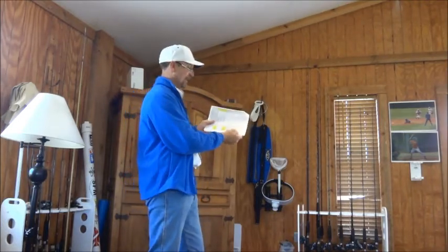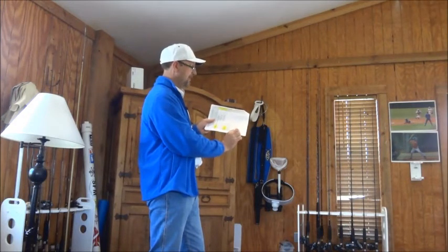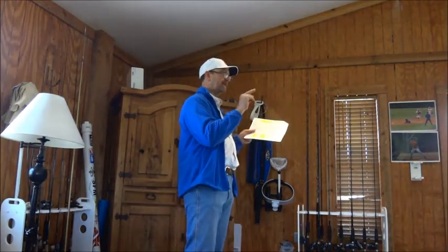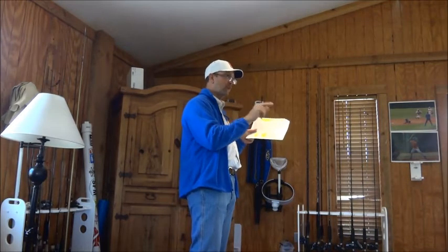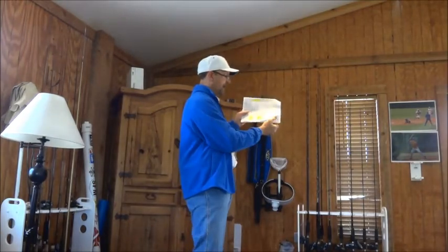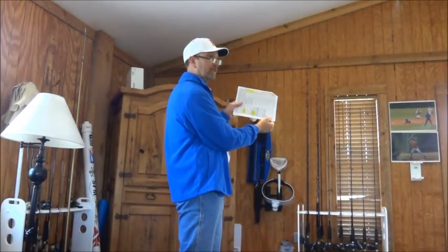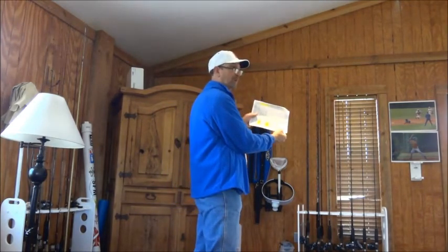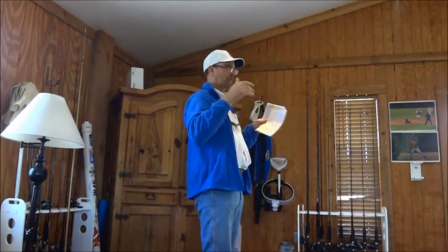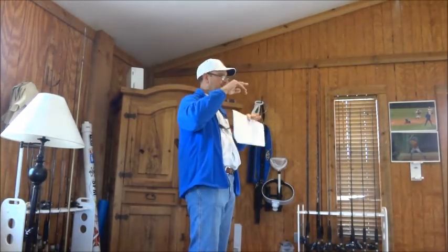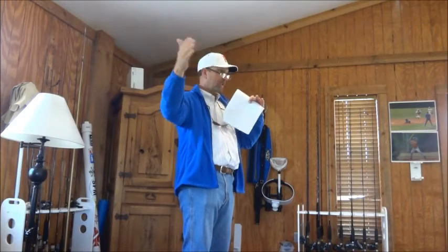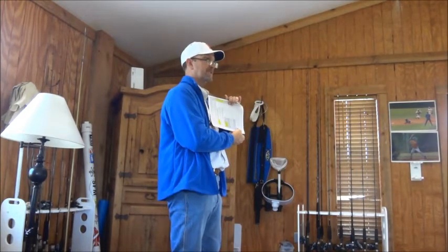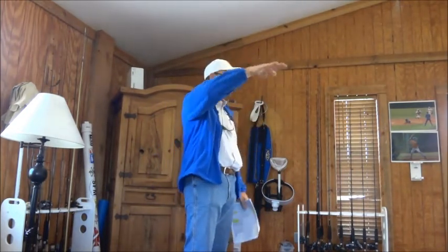And so what I do then, and this is my crazy, I try to take it so many steps further. I say, this last column here, if I have a calculator that says, if I continue to use water at the same rate as this month that I just added, it says you've got 18.3 months left at that rate. But then we kept climbing. It went down to 6.1 months. So our water use kept going. As our water use increased, the amount of months that I could burn at that rate shrunk. I'm using them faster. But then we reduced our pumpage, and you see it increased to 7.7. So what I do is I've added a predictor.